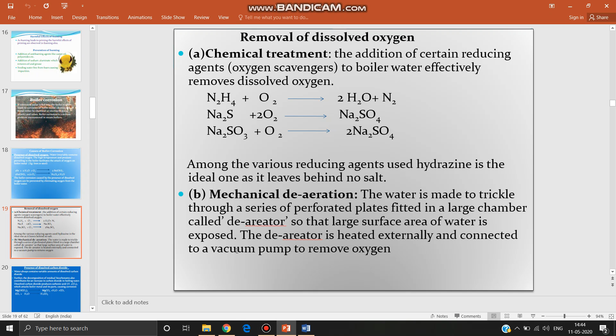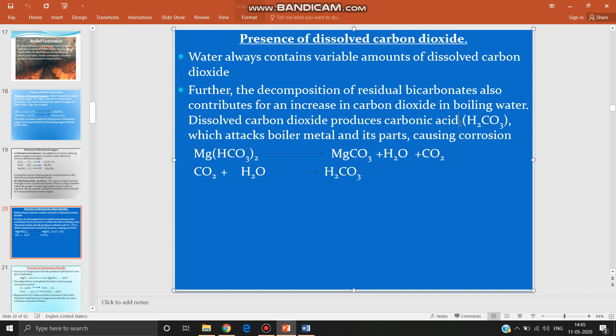Now, another reason for boiler corrosion: presence of dissolved carbon dioxide. Water always contains variable amounts of dissolved carbon dioxide. Further, the decomposition of residual bicarbonates also contributes, as we have seen in the estimation of total hardness. On boiling, bicarbonates are converted into carbonates, but at the same time, carbon dioxide also will be evolved. So, bicarbonates are also one of the sources of dissolved carbon dioxide. If the water contains bicarbonate, that increases carbon dioxide in boiling water. Dissolved carbon dioxide produces carbonic acid when it undergoes hydrolysis, which attacks boiler metal and its parts, causing corrosion. So, this is another reason for boiler corrosion.